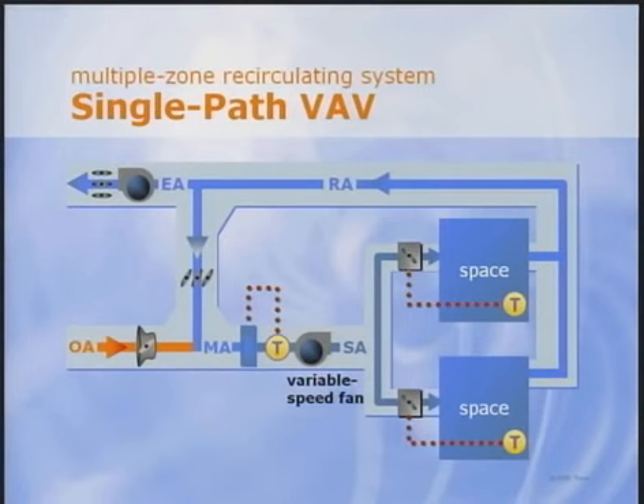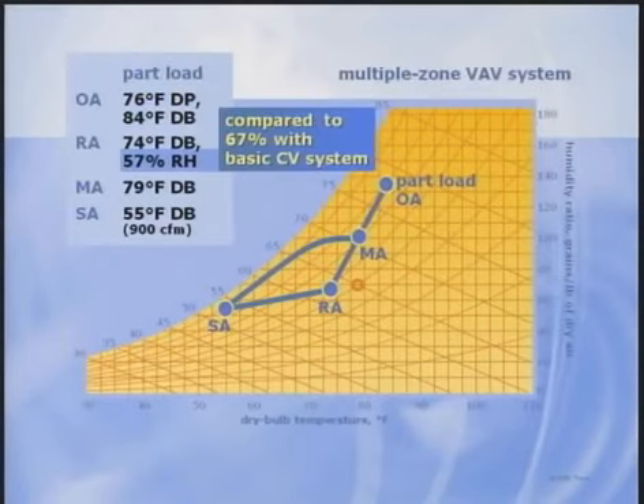around 55 degrees. An iterative psych chart analysis at design dew point shows that as the sensible cooling load decreases and the VAV boxes reduce primary airflow, the cool, dry primary air limits zone relative humidity to about 57%. So this VAV system example also meets standard 62 without direct humidity control. Clearly, dehumidification depends on system type, configuration, and control. We have analyzed many different systems and presented various publications listed in the bibliography.